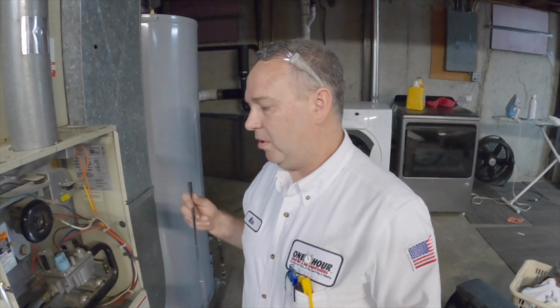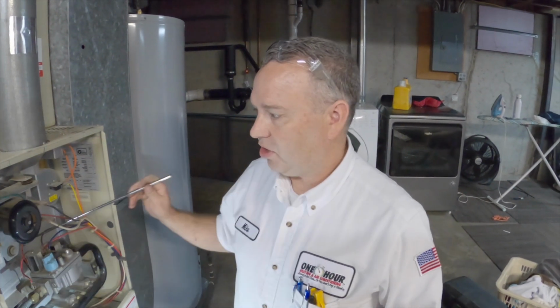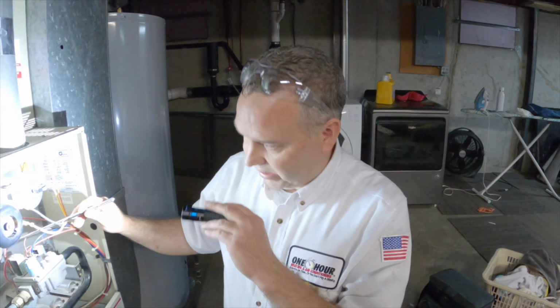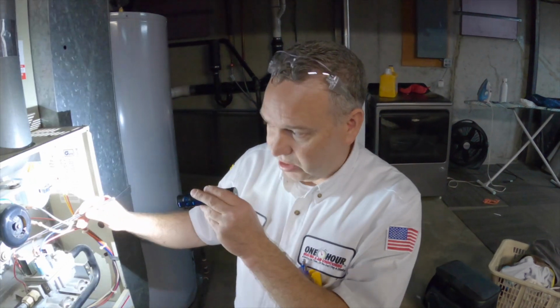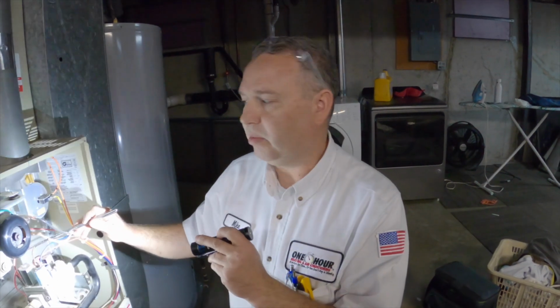This furnace is unsafe to operate. When you find something like this, the American Gas Association states we have to shut off the gas to the furnace until either this heat exchanger is replaced or the furnace itself is replaced.